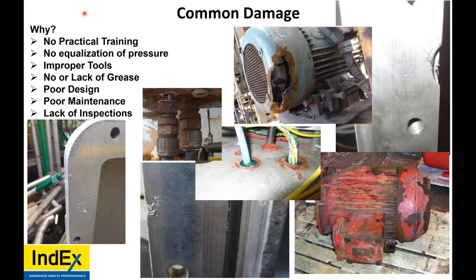Now, when we look at common damages of EXD devices, well, there's many. Corrosion, water ingress is a big problem, whether it's in the device or not. Rust, damages on the edge, probably from somebody with a screwdriver. Then we have other ones where it looks like pitting, old age, other things going on. A weird combination of a putty and liquid barrier glands somehow. Glands completely rusting away. And then damaged edges, perhaps from dropped covers or dropped boxes.